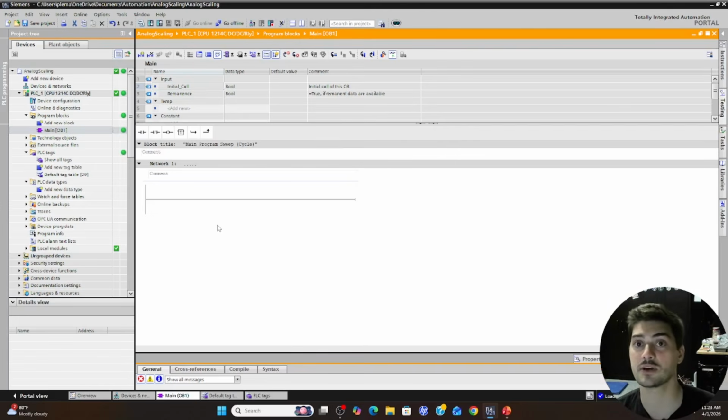Now, it's important to note that every PLC manufacturer and every analog input card can be a little bit different, so you need to check the specs for what the raw input signal is for your card. Some Allen Bradley cards will use 0 to 32,000, basically maxing out what an integer variable can hold.